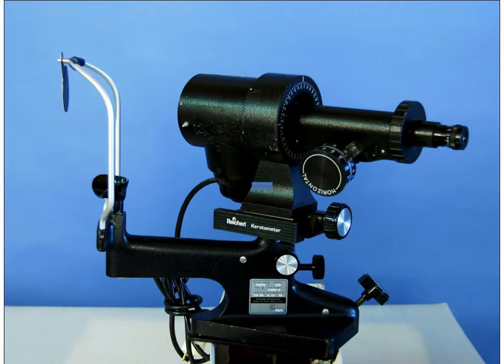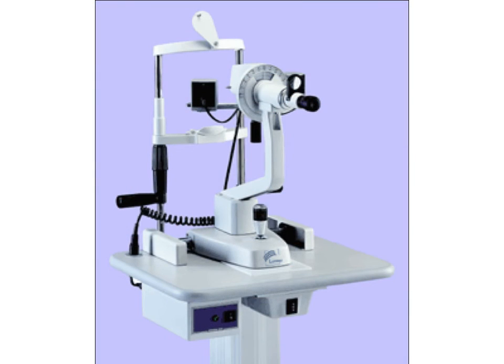This is a one-step keratometer. This is the sort of keratometer that you are used to using. The assumption that this keratometer makes is that the meridian of greatest flatness of the cornea and the meridian of greatest steepness are orthogonal, that they're perpendicular to each other. This is a Javal two-step keratometer, which makes no such assumptions. At Mass Eye and Ear, where I did my cornea fellowship, we had some of these. I don't think I've seen them outside of that clinic, though.